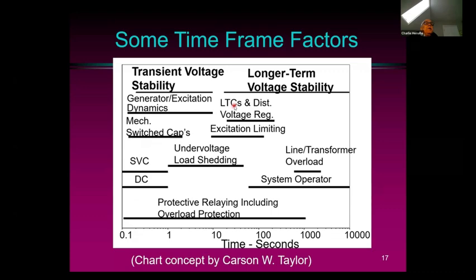And load tap changers take longer to operate. Exciter limiters can allow temporary overload of generators. This is an option used more frequently these days, which of course is not a good option for a firm load that you're trying to supply. But this can and has been used with a certain time frame, maybe 1 to 10 seconds. And then we have the system operator who, being a human being, would take some time to come into play, maybe up to a few minutes.